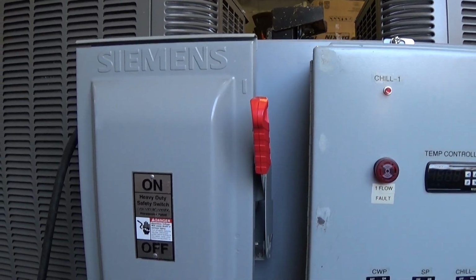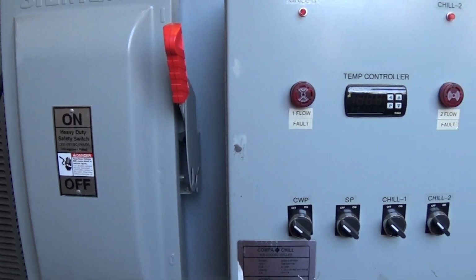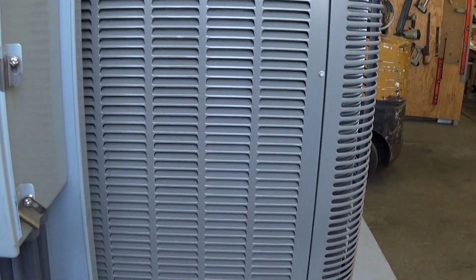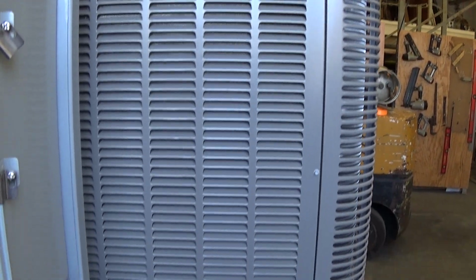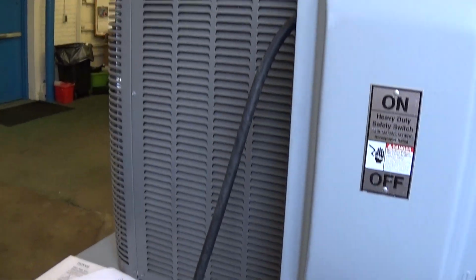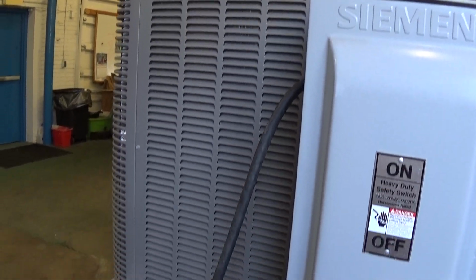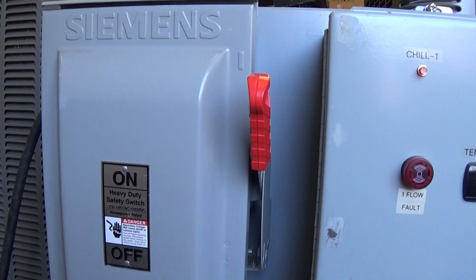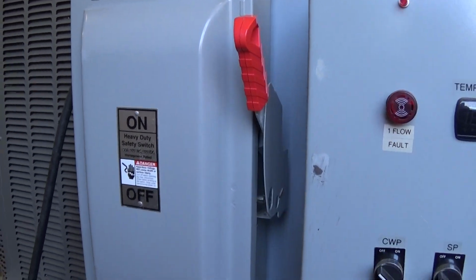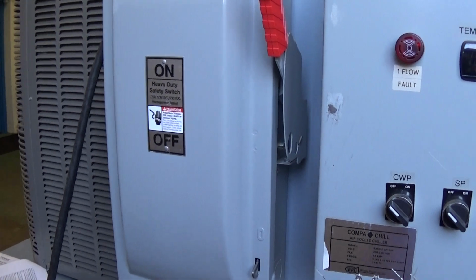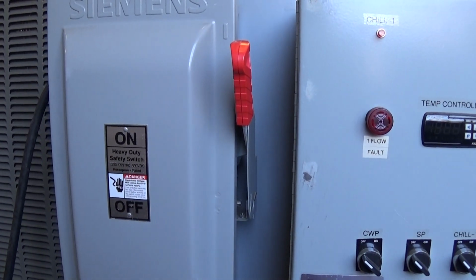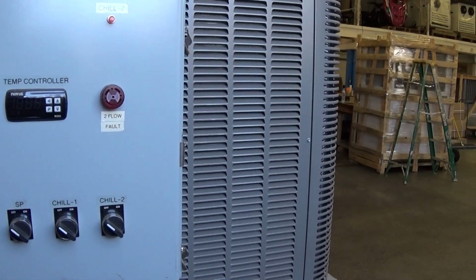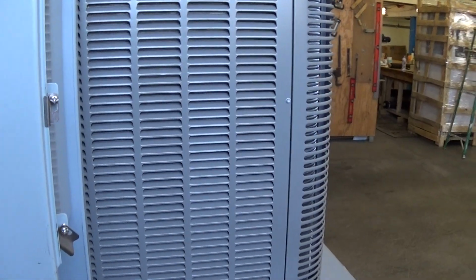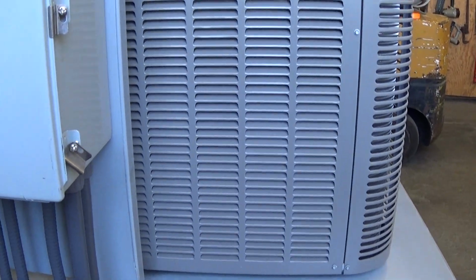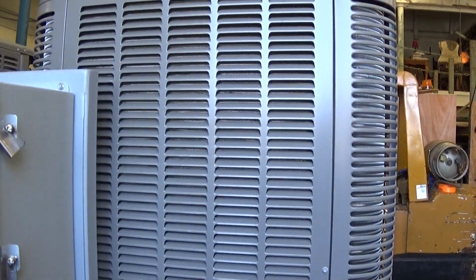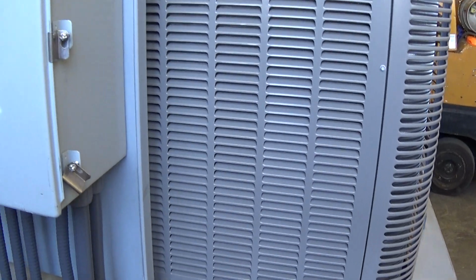But as long as that power is live right now, the crankcase heaters, which are on the compressors in each compressor condenser assembly here, those heater bands are on. There's actually a thermostat that controls those heater bands to be on or off. I think it's like below 70 degrees they'll be on. So it's always nice to have power live to the chiller because that keeps the refrigerant from sludging or being too cold on a cold startup if you had the system off for a while.